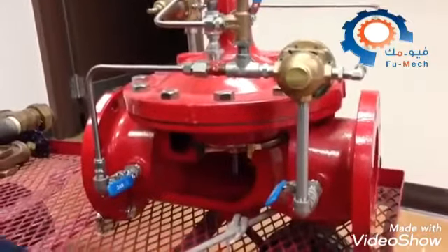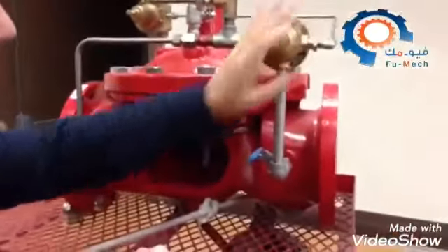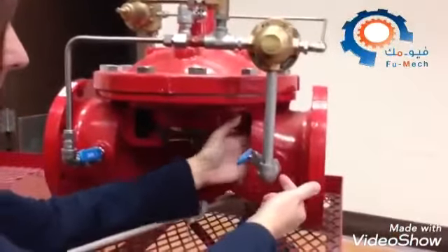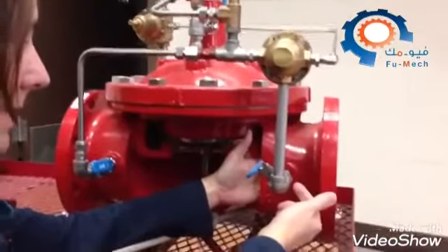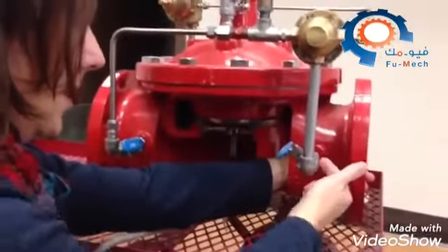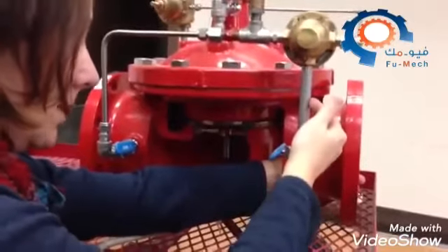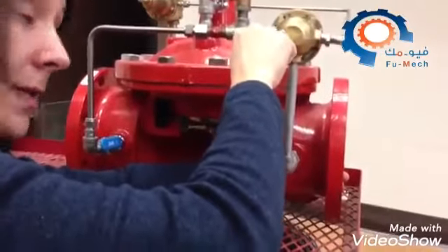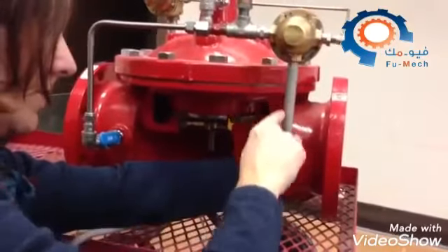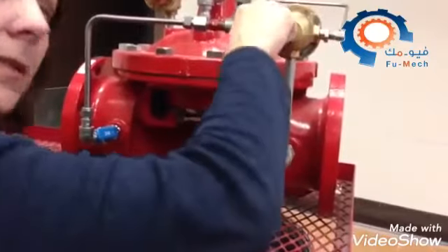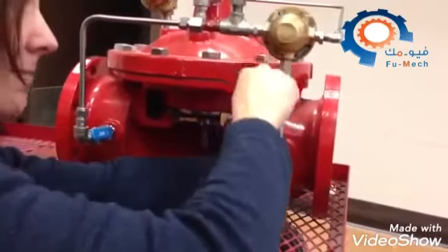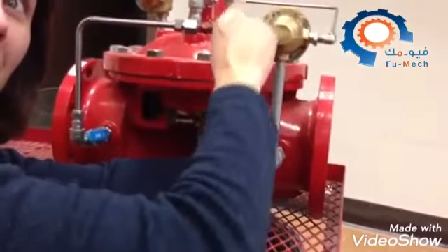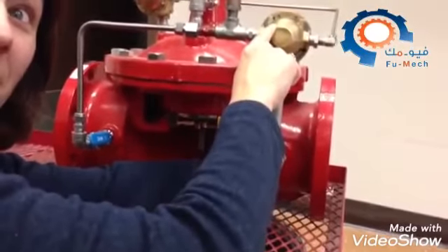So the next step of this whole process is, if we look here, this valve is controlled by the downstream pressure. So you can see the pressure inside this main pipe connection here is going to be the same pressure that's in here, the same pressure that's inside the body here. So that pressure in the downstream side of this valve is transmitted through this line into the interior. And it doesn't matter which way the water is going. The pressure is still going to be the same. Does that make sense?